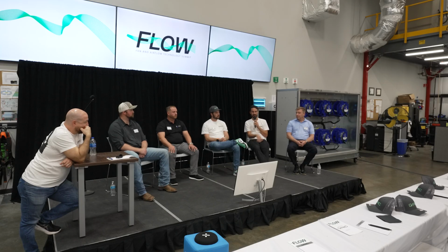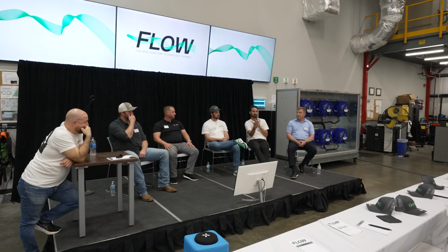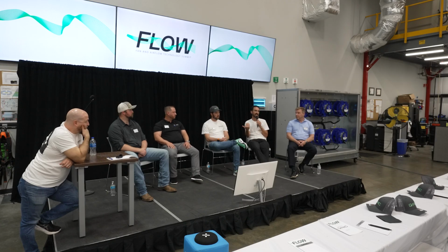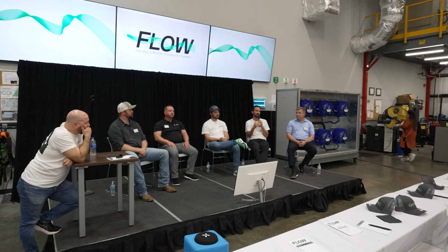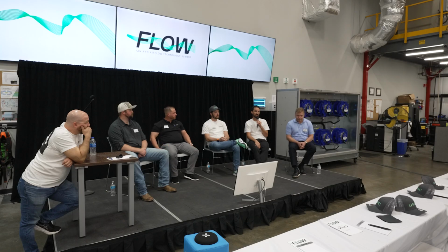I was talking to some people in the R&D area. When you're sizing a fan array, you always add an additional fan to the system, and you have to deal with the consequence of that. You need larger conductors, larger wires, larger conduit, because you added another motor. In the MPF, the way we're designing it, it may have an additional motor in the system, but from a specification perspective, it only needs to use that added mechanical component when it needs it. So an array might say 60 amps on a schedule, and the MPF might be 50 amps. It seems minor, but we're able to reduce the total cost of the fan system by not having that burden.